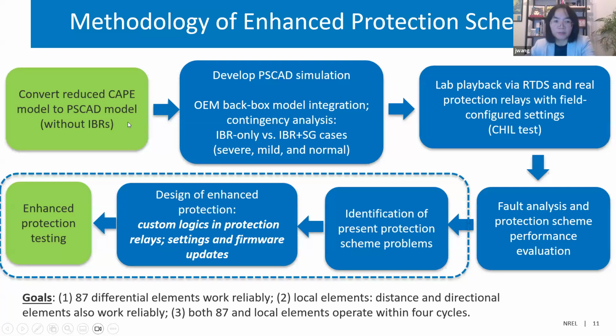There were a lot of challenges there because of the zero sequence impedance calculation. We have a report we are drafting now, so in that report you can see what we did for this calculation and model validation. And after we develop the PSCAD model, we plug in the OEM black box model, and we run through the normal and N-1 contingency and also the IBR scenarios, to run through all the different scenarios. Then we did the playback in the RTDS and connected with the real hardware relays configured with the field settings through controller hardware-in-the-loop testing.